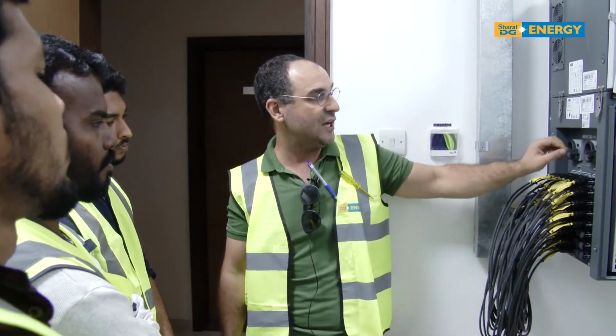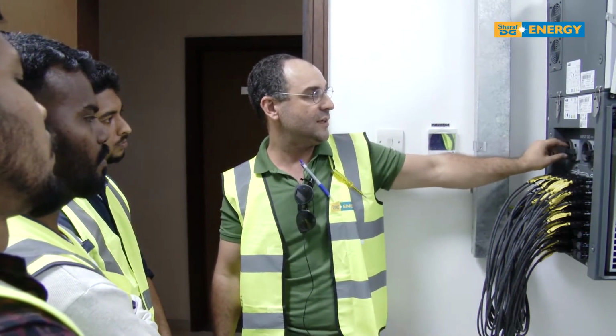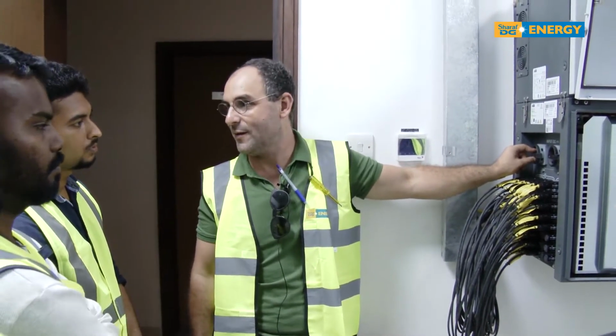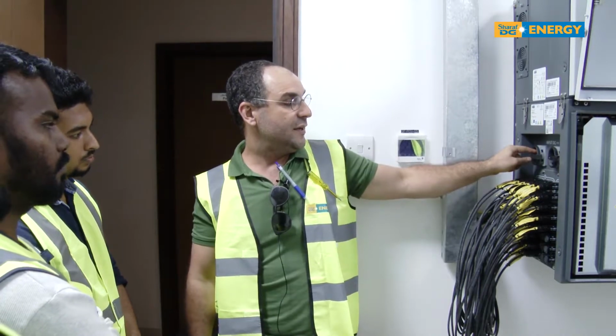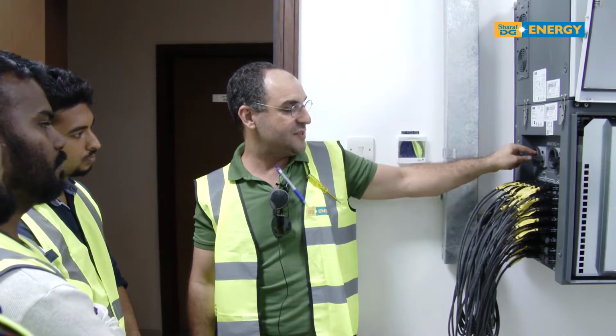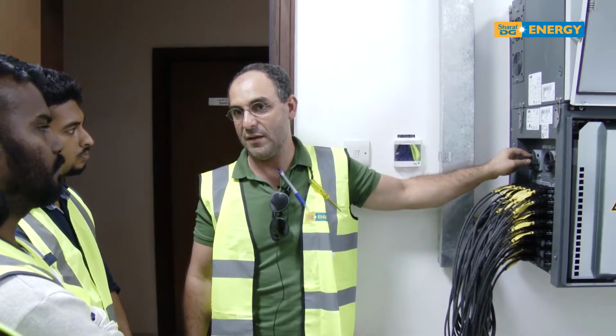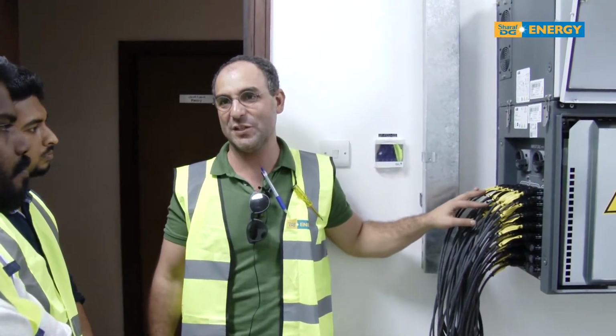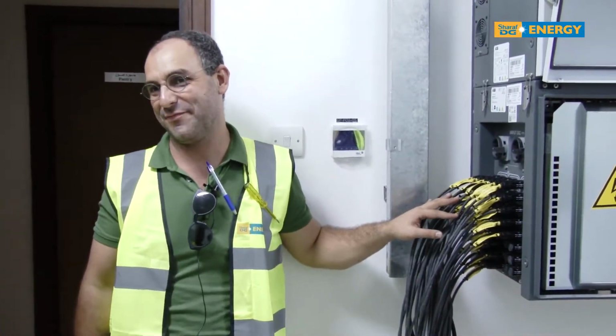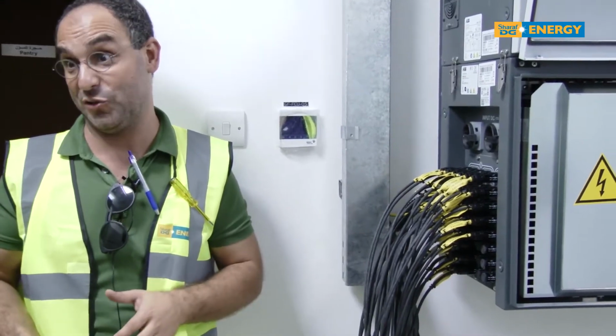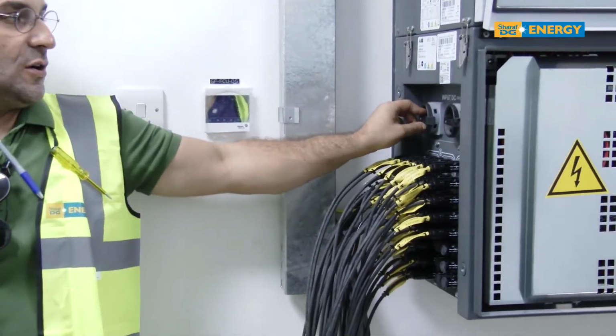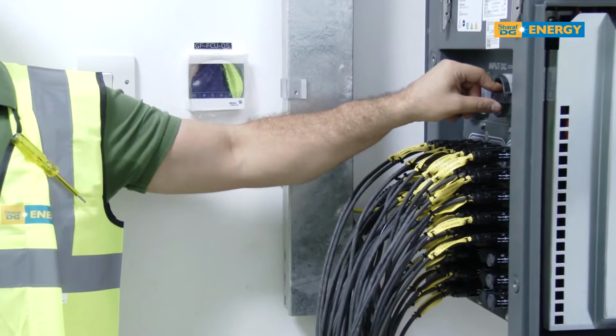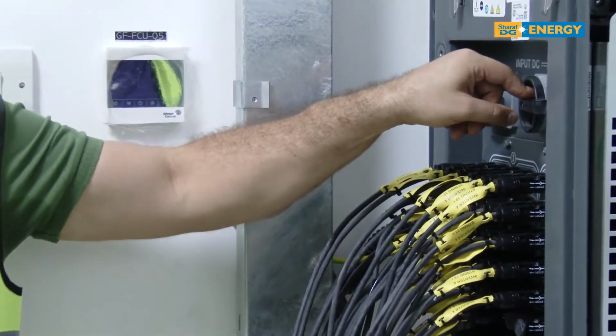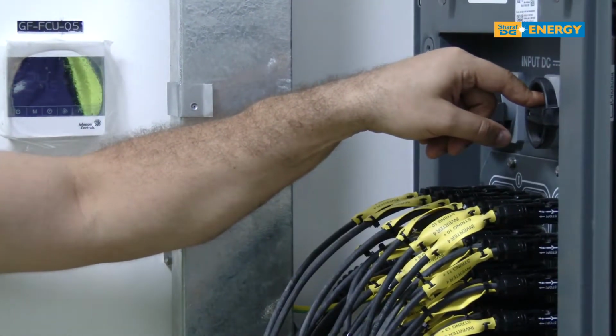But if I want to shut down the DC side, I just need to rotate these two switches. So what happens? Right now the system is running on VMPP. If you measure any voltage here, you'll measure VMPP, because the system is under load. If I close these switches, then whatever voltage you get will be VOC.